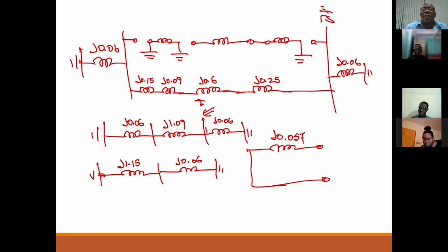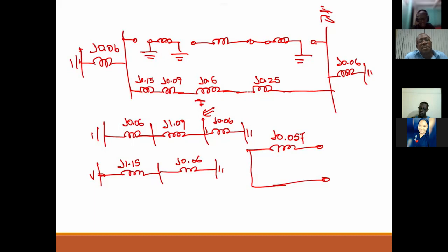Ms. Gray? Yes, sir. Why would that be incorrect? Sir, would you use like the 13.8? No, I didn't ask you to. I said, why would it be incorrect? I don't want you to give me a value, just tell me why it has to be incorrect. Sir, 69 kV is a transmission voltage. Use the generator voltage, sir. Absolutely. The fault, Mr. Duncan, is on the generator bus.